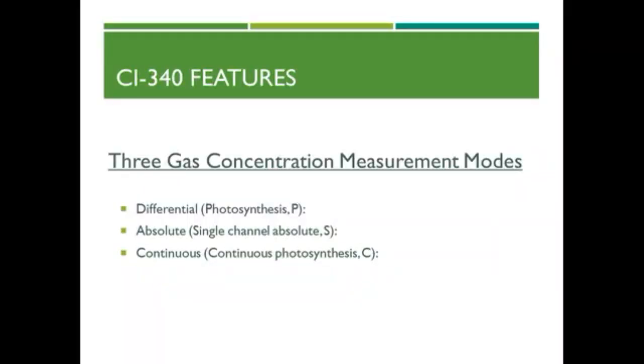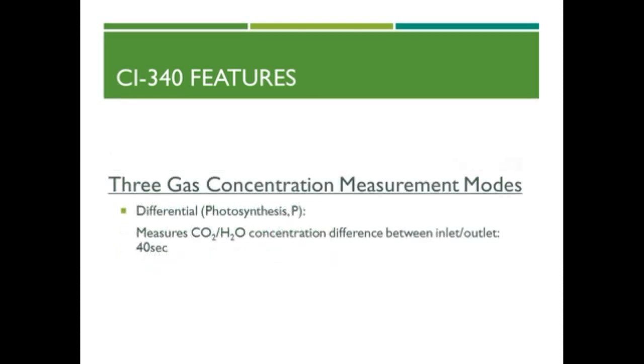There are 3 main modes for measuring gas concentrations in the CI-340: differential, absolute, and continuous mode, designated P, S, and C. Differential mode, or P, measures photosynthesis. This mode quantifies carbon dioxide and water concentration differences between the inlet and outlet gas flow.